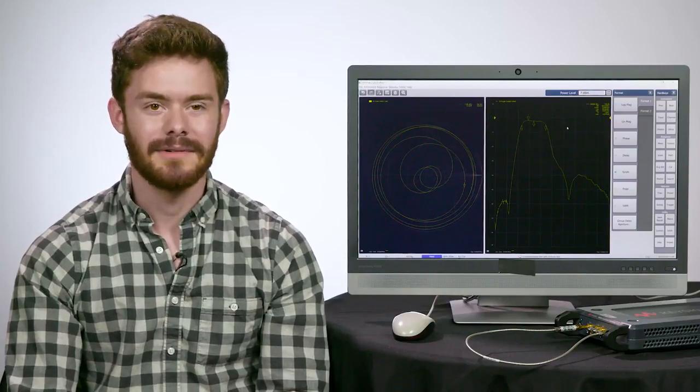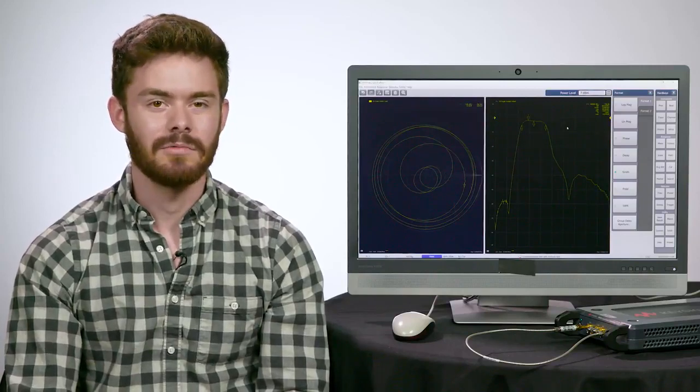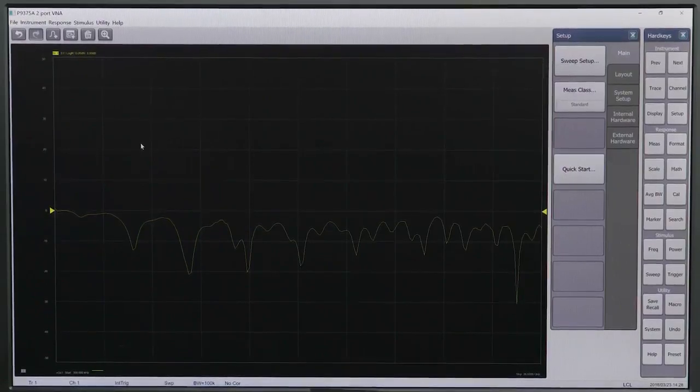Your device will show up in that window. Select it and click Run. Notice that this soft front panel has the same user interface as the Keysight benchtop PNA and ENA, as well as the modular PXI VNA.